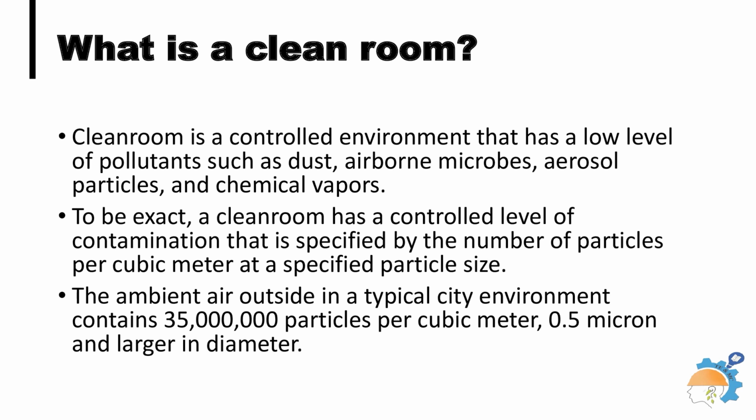There should be no more than 2 orders of magnitude difference in cleanliness classification between connecting spaces. For example, it is not acceptable for a class 100,000 clean room to open into a class 100 clean room, but it is acceptable for a class 100,000 clean room to open into a class 1,000 clean room.